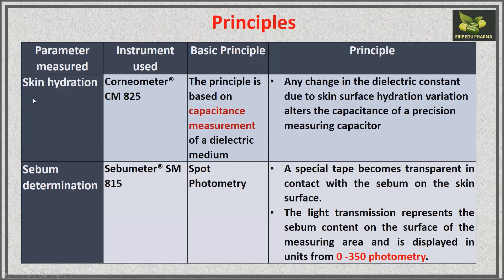For skin hydration, the instrument used is the corneometer. The basic principle is that it is based on capacitance measurement of a dielectric medium. Any change in the dielectric constant due to skin surface hydration variation alters the capacitance of a precision measuring capacitor. Even very minute changes due to an increase in water content are measured by this instrument.